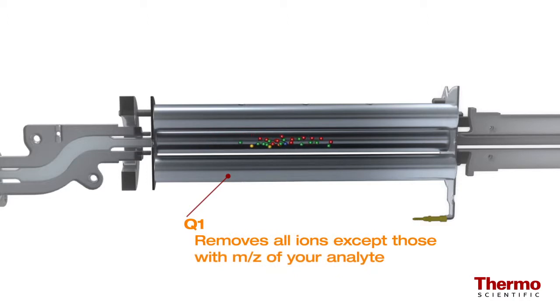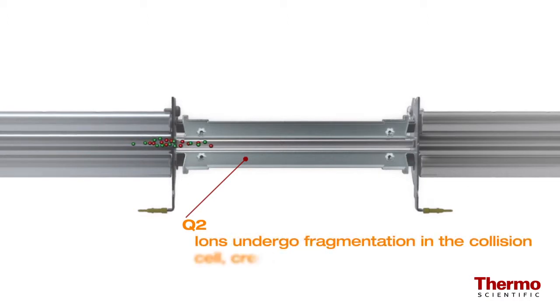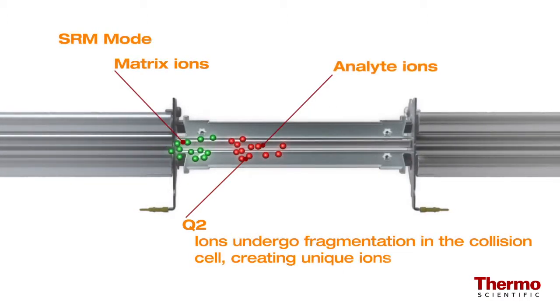As with a single quadrupole GC-MS system, the first quadrupole will eliminate all ions except for the ones with the mass-to-charge ratio of your analyte. However, if a matrix ion of the same mass coelutes with your target, a single quadrupole system cannot differentiate the two.